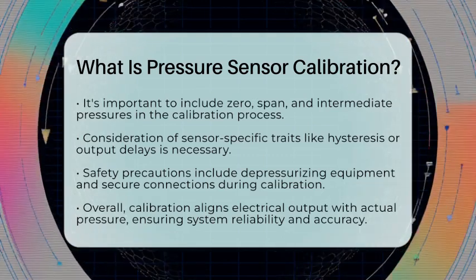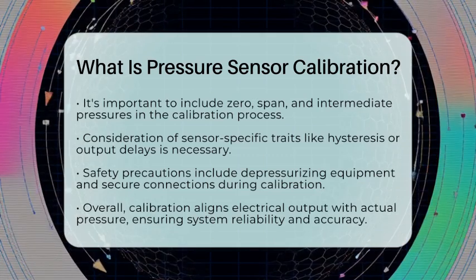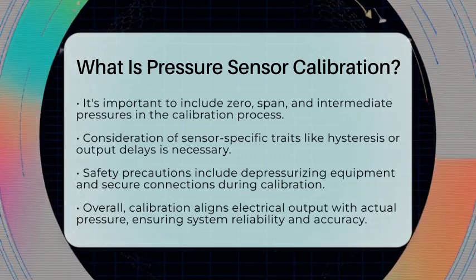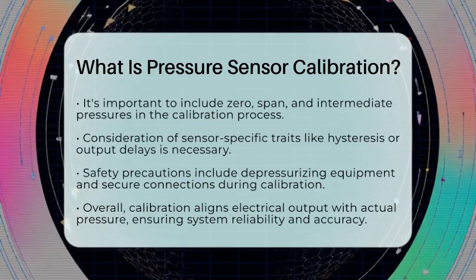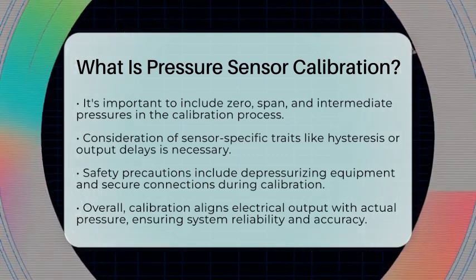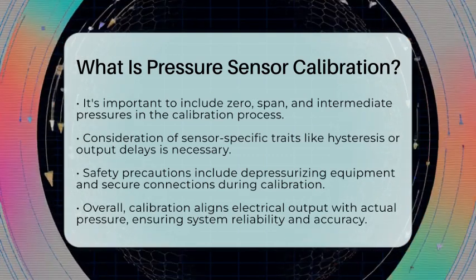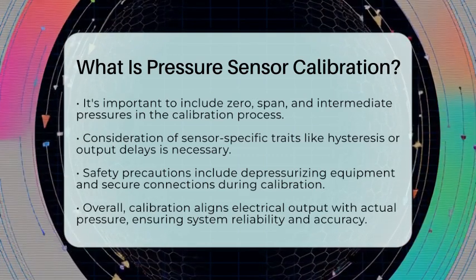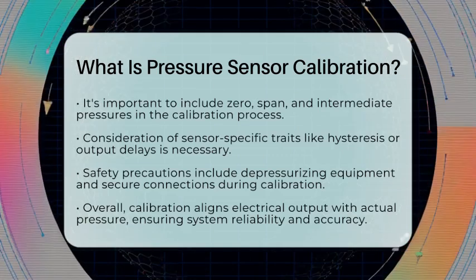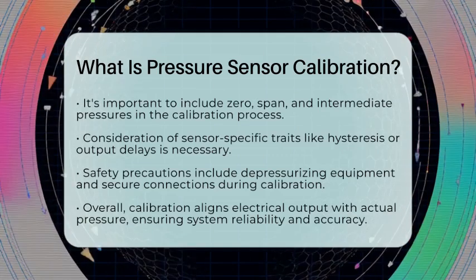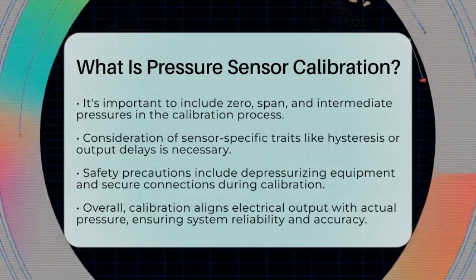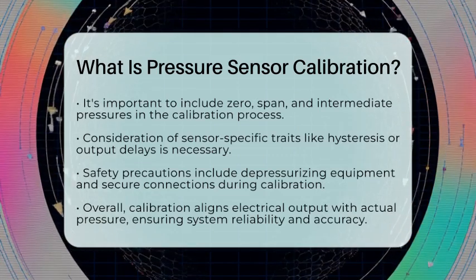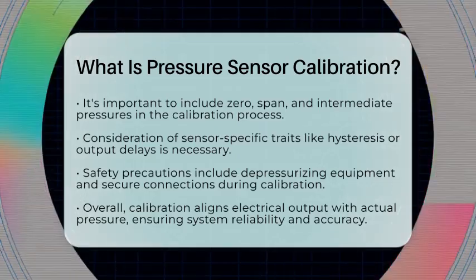Safety is key during calibration. Equipment should be depressurized and properly connected to avoid accidents. Overall, pressure sensor calibration is about aligning the sensor's electrical output with the real pressure it measures. This process keeps your systems reliable, accurate, and compliant with standards, whether you're monitoring industrial processes or designing embedded systems.